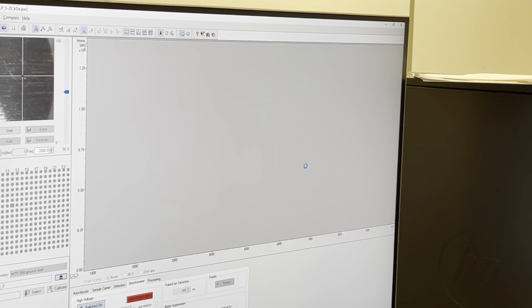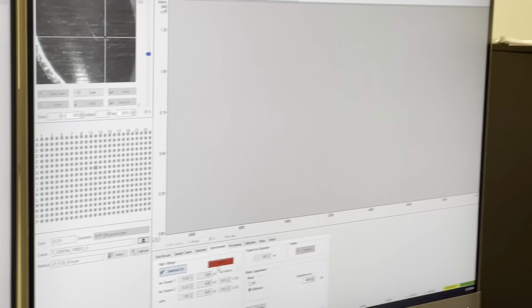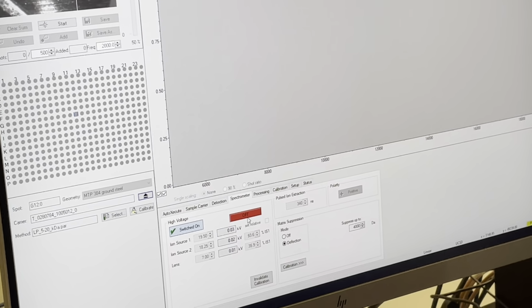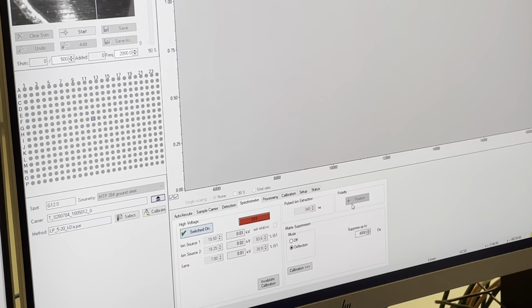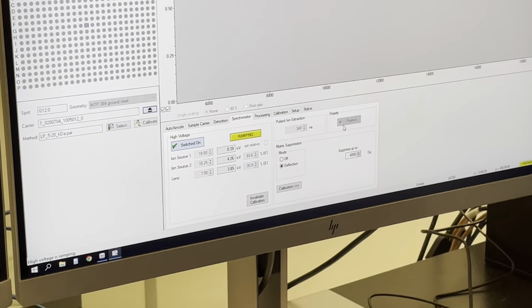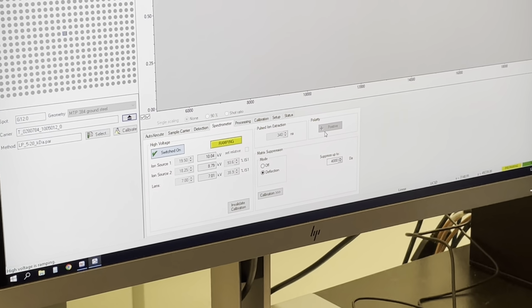Once you load the method, this indicator is going to change to yellow and then change to green. It just takes a few seconds to ramp up the high voltage. It's right here, ramping up the high voltage.